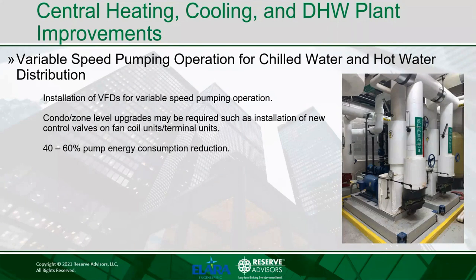Another energy efficiency measure that requires lower capital investment and is not a large construction disturbance is installation of VFDs on buildings' hot water and chilled water pumps. Typically, high-rise residential multifamily buildings have chilled water and hot water distribution pumps that distribute space conditioning water from the central plants. Typically, what we see is these pumps operate at constant speed, regardless of how much cooling or heating is needed at the building. So the goal by installing variable frequency drives here is to minimize pumping energy during low load conditions. For instance, when it's really not very hot outside during shoulder months, those pumps don't need to run as hard as when it's really warm outside. So it'll be important to take advantage of those low load conditions to save energy. And with these types of upgrades, we would typically see 40 to 60% pump energy consumption reduction.